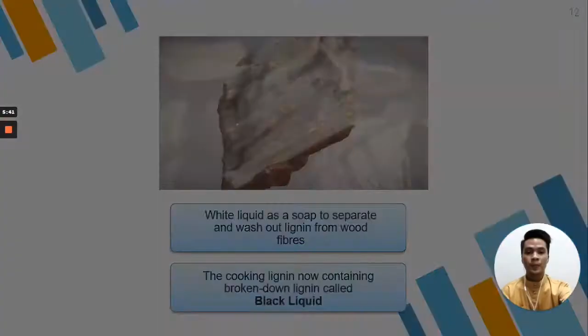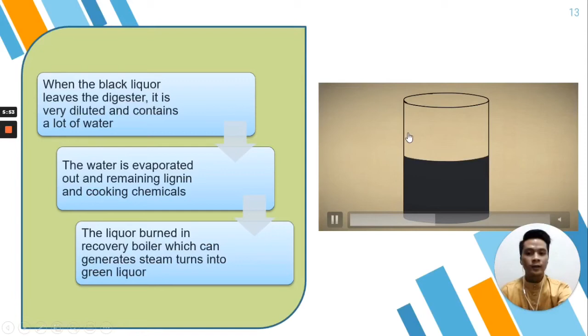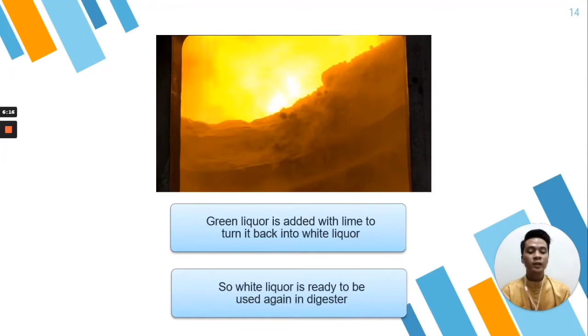So what will happen to the black liquor? When the black liquor leaves the digester, it is very diluted and contains a lot of water. So the water here will be evaporated, leaving the lignin and cooking chemicals. Alright, the liquor will be burned in a recovery boiler, which can generate steam and turns into green liquor. And what happens next to the green liquor? The green liquor will be added with lime to turn it back into white liquor. And this white liquor can be used again at the beginning of the kraft process, which is the first step, to remove lignin from the wood fiber.